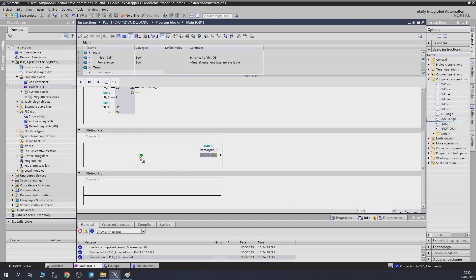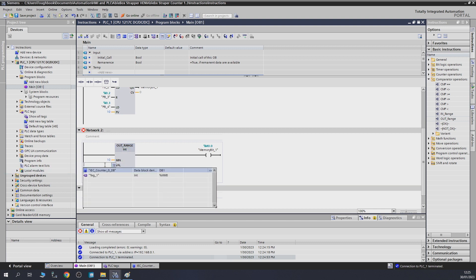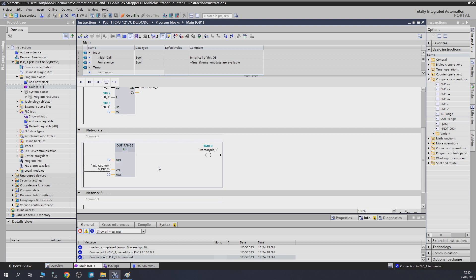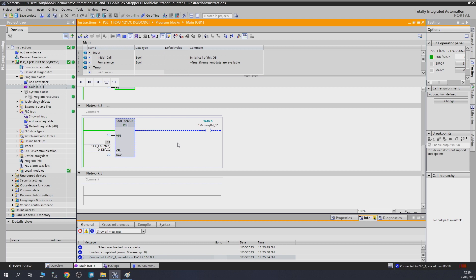Next up is Out of Range — the opposite of In Range, looking for values outside the range. We give it 10 and 20 again and connect the counter as the input. Currently sitting within range, the output is off. For Out of Range, the value must be below 10 or above 20 for the output to activate. Going up, as soon as we hit 21 — which is out of range — the output goes on. That is Out of Range.